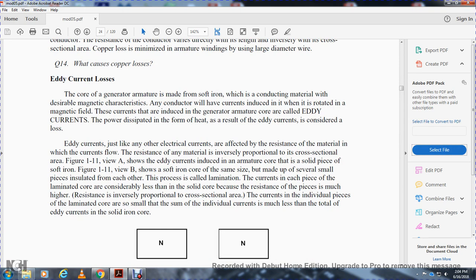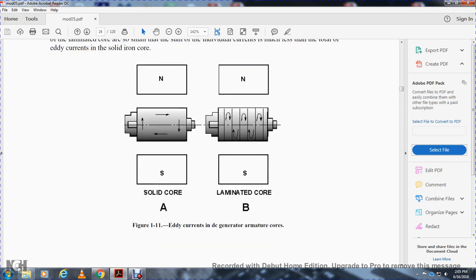Eddy currents, like other electrical currents, are affected by the resistance of the material. The resistance is inversely proportional to the cross-sectional area. Figure 1-11A shows the eddy currents in a solid piece of soft iron armature core. Figure 1-11B shows a soft iron core of the same size made of several smaller pieces insulated from each other — this process is called lamination. The currents in each laminated piece are considerably smaller than in the solid core because the resistance of each piece is much higher. The sum of all individual currents in the laminated core is much less than the total eddy currents in the solid iron core. Eddy currents are kept low by making the core of many thin sheets of metal. The laminations of small generator armatures may be as thin as 1/64th of an inch, insulated from each other with a thin coat of lacquer or by oxidation.